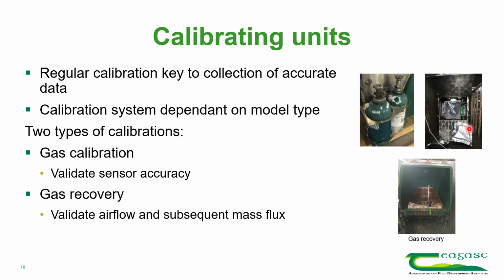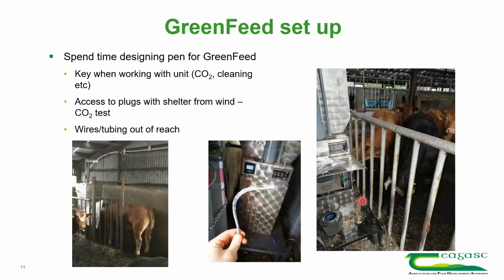And if there's any drift, a calibration coefficient is calculated, or perhaps the sensors need to be blanked. Then there's also gas recovery, where we pump a known amount of CO2 through the unit and see if the machine is able to pick up that known amount. Based on that, we calibrate the airflow going through the unit. Both of these calibrations are used within those two equations which I previously showed.